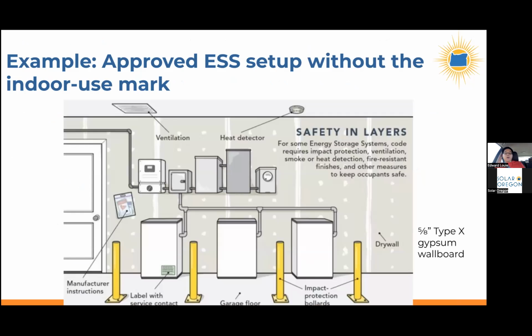And so in an area where you have vehicles that can back into or hit the batteries, like in particular a garage or driveway, you're required to have bollards to protect the batteries. And then if it's inside a garage, you need to have a heat detector and also a vent. A vent to allow the battery, if it were to catch on fire or overheat, and then the way modules typically, even if there's no flames shooting out of the battery, when they overheat or go into thermal runaway, oftentimes they degas and produce a lot of toxic gases that aren't really good to breathe. And so then you need to have a vent for the gas to escape out of that space.